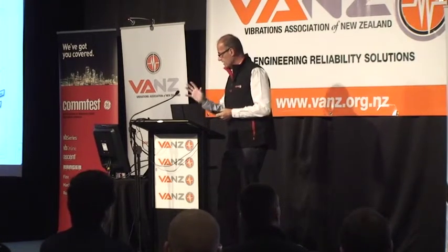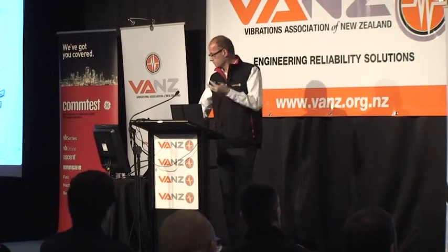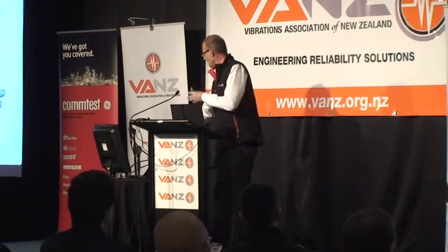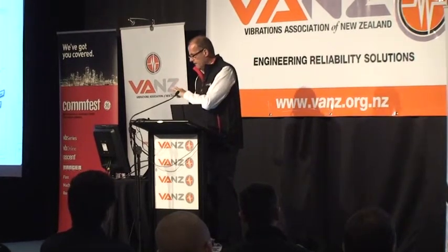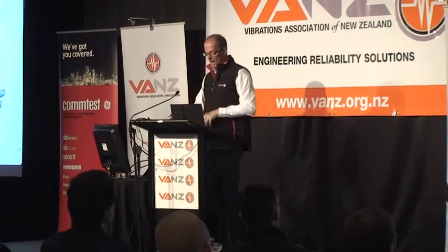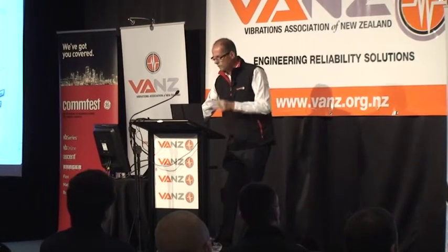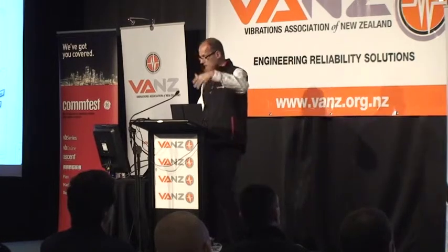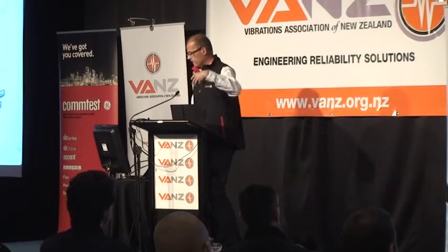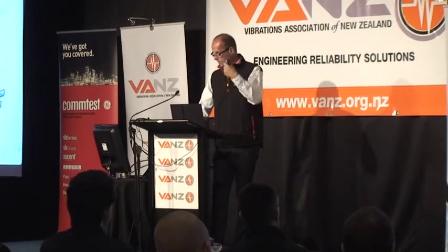The challenge is we need to understand this sort of thing. How much time is it from this point of potential failure, that's the P in the PF interval, to functional failure? Because if that was a very short period of time, we need to be taking measurements very frequently in order to detect it so that we can respond.